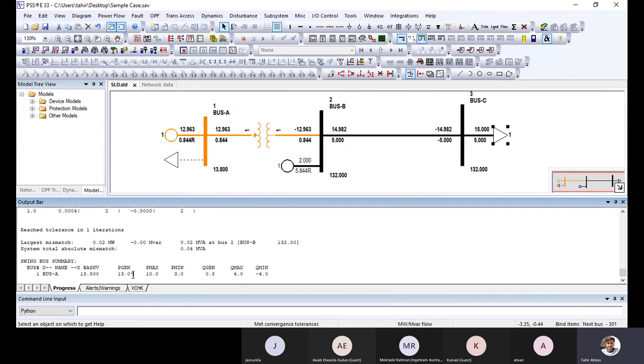In the report bar here on the Pgen, can you see that there is an asterisk? This basically gives you a hint that the swing bus is telling you that demand is increasing and you need to add a generator. So the swing bus is basically giving you a hint that demand is increasing. You need to add another generator.